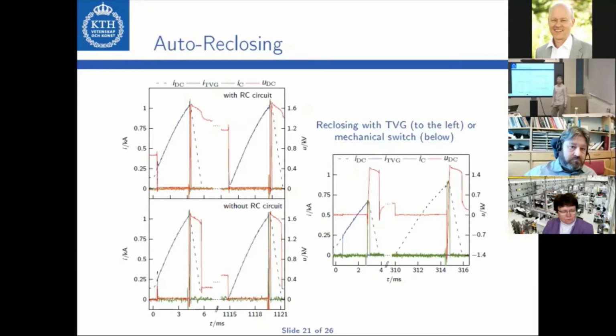The mechanical switch is now also operated not as a disconnector, but as an arcing switch, so it is operated with an arc. At this point, the test current exceeds the trip level, and now the circuit breaker should operate. However, this is the time when the mechanical switch starts to open. After some time, the mechanical switch can take the transient recovery voltage, and that's when the injection circuit is activated to now extinguish the arc in the mechanical switch, similar to as it was done for the triggered vacuum gap before. As you can see, the second current pulse is higher than the first one. And that's because in this kind of reclosing strategy, one cannot utilize proactive commutation. But this also works reliably.